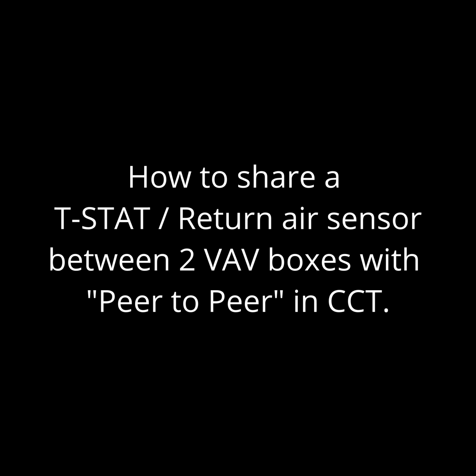At this point, I could have run two dedicated return air sensors to the same location, one for each VAV box. There would technically be nothing wrong with that, and that would work. Now, that would require me running two wires to two different boxes, costing me a little bit of time, but it's not the end of the world. But there is a better option where we can run one single return air sensor and actually share that value over the MSTP trunk via peer-to-peer.